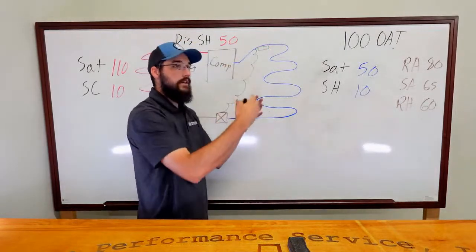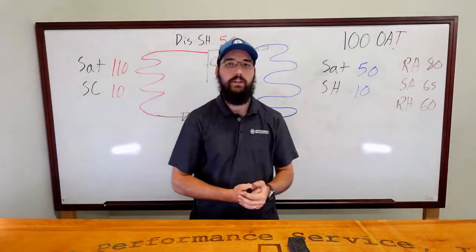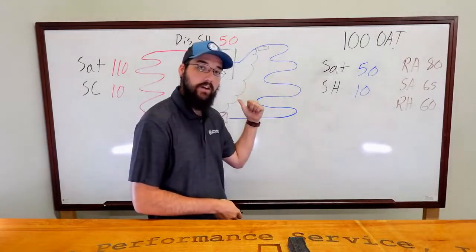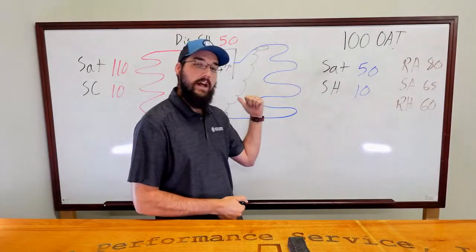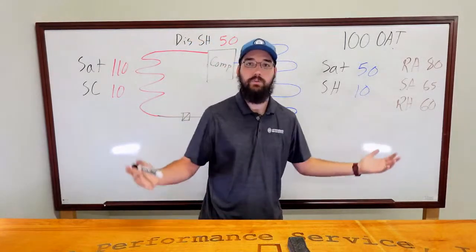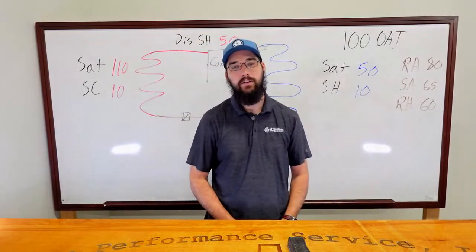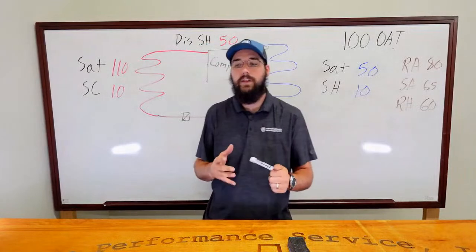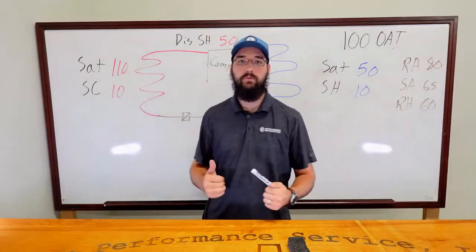And it's not tripping constantly. Let's say on a call like this, you're there for 30 minutes to an hour looking at these readings, trying to interpret them, and it's able to run that whole time. What you didn't know is it just turned back on 5-10 minutes before you walked up to it. You give it an hour and you're really not sure. So you say, I need to come back with somebody more experienced than me, and 20 minutes after you leave, it trips back out. It genuinely works out that way. That's the kind of stuff that, again, is right place, right time. These are hard things to work through.